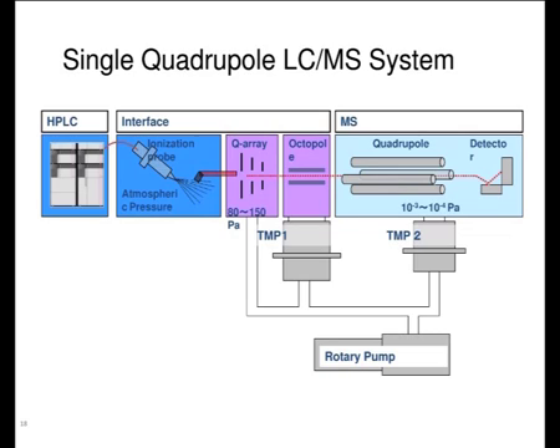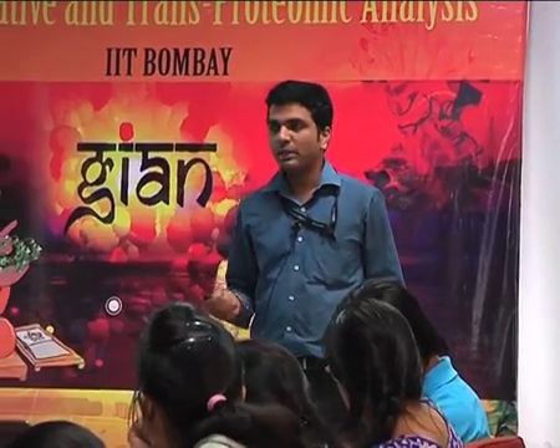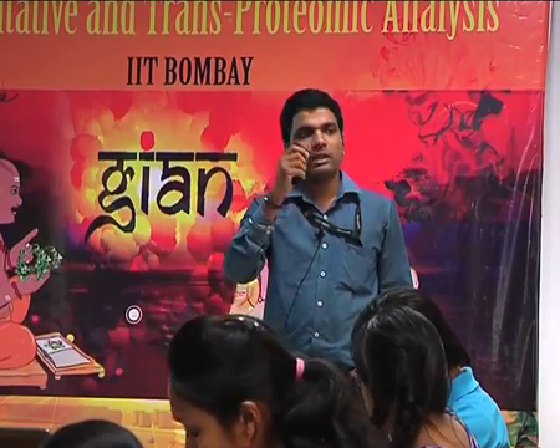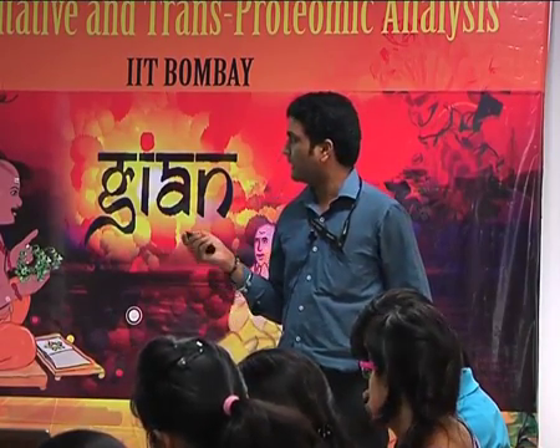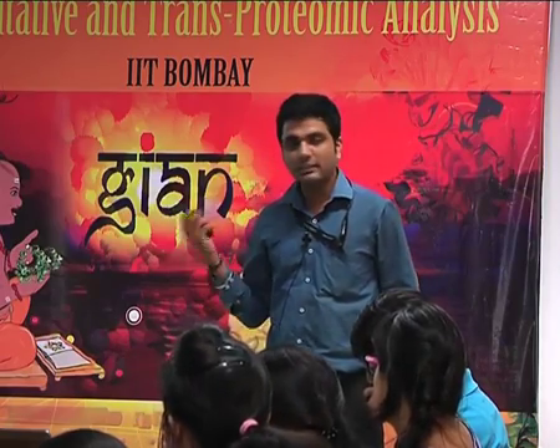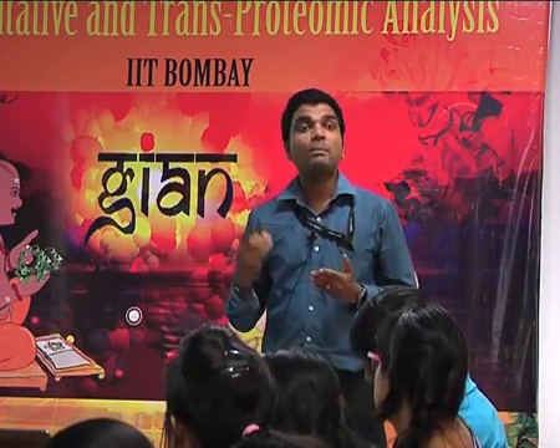For the ion guides we provide RF frequency. Why RF frequency? Because, as I told you, the RF frequency helps with the focusing of the ions. Then it goes to the quadrupole. In the quadrupole, along with the RF frequency, we also give DC voltage. The DC voltage is used for the selection of particular ions, and the RF voltage for the movement of the ions in the forward direction. For example, if you want to analyze a particular ion of a particular mass-to-charge ratio, the instrument is tuned in such a way that, based on the molecular weight, the DC to RF voltage is already tuned, because for this LCMS or any LCMS, before doing the analysis you have to calibrate the LCMS.